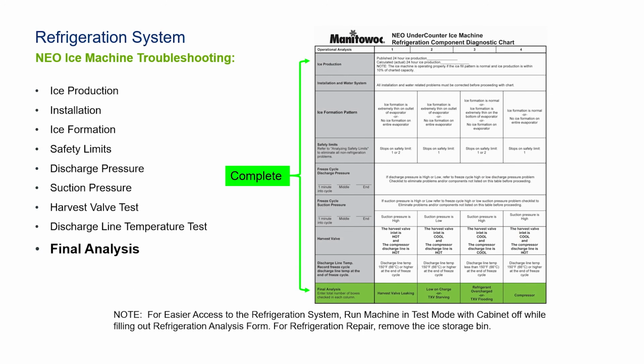We're not going to go deep into this refrigeration bit, but let's say that you have verified everything in your sequence of operations works without a problem. You are moving good water, refrigeration is running, and you're not sure what's going on. We do have a symptom number 2 flowchart. It's a checklist more than a flowchart to troubleshoot your refrigeration system. You have verified cleanliness. You have verified water fill. You have verified water flow. You have verified the refrigeration system is running and you are just not making ice, or you are not making ice at a fast enough speed, which this ice machine should not take 45 minutes to make ice, especially if it's in a well-conditioned area.